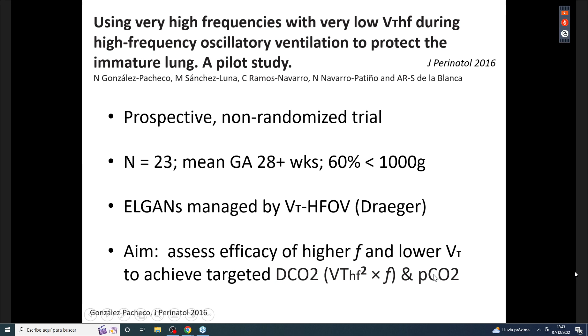And here's a pictorial of the baby log VN500 that they were using. It's important to note that they can give sigh breaths, and this is what a sigh breath looks like in this particular system. And there are brief pauses in high frequency breaths when a sigh breath is given, unlike the jet, for example, where if you give a sigh breath where the peak pressure does not exceed the jet's peak pressure, you will continue to get jet high frequency support on that conventional breath.